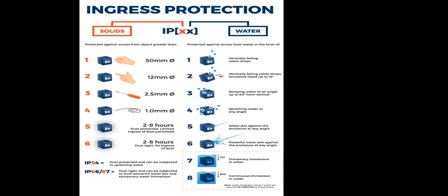If I decide to install a panel in an open space and select an IP42 protected panel, what will happen? Let us not even consider the solid objects, assuming I am installing outside. But what about rain? It gives protection against vertically falling water drops, with the enclosure tilted up to 15 degrees. But at a 15 degree angle, the rain is splashing over this panel, so it will not protect. The moisture will go in and it will not perform. That is why it is so important that when we select any component, we ensure the correct protection is selected.